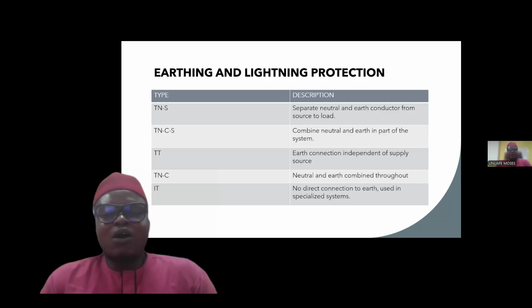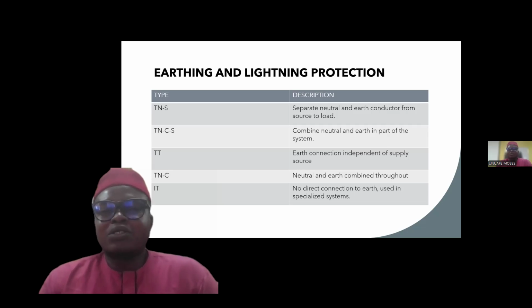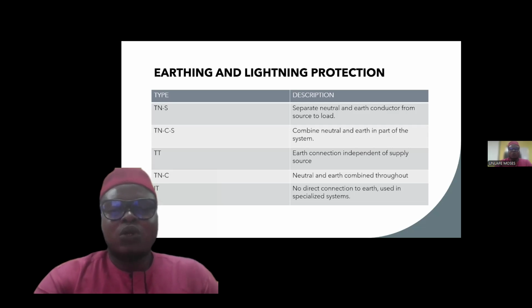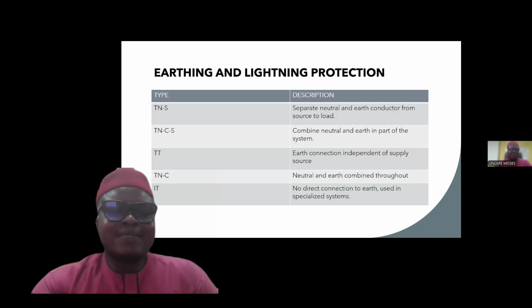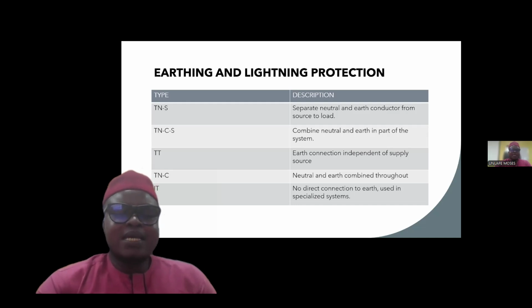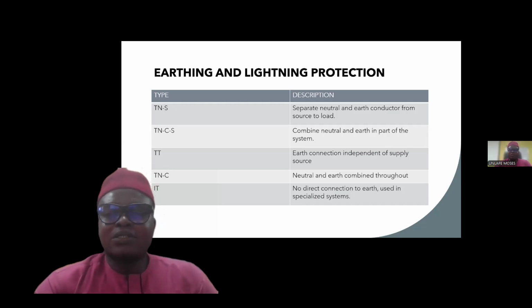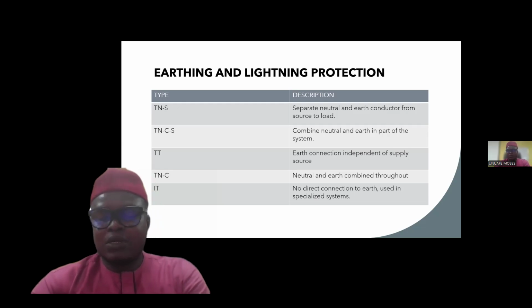I want you to understand that there are other types of earthing system. We have the types of earthing system, which are TN-S, TN-C-S, TT and TN-C. TN-S separates the neutral and the earth conductor from source to load, while TN-C-S combines the neutral and the earth in part of our system. Then the TT, another type of earthing system, has an earth connection independent of the supply source. Then TN-C has the neutral and earth combined throughout the installation.